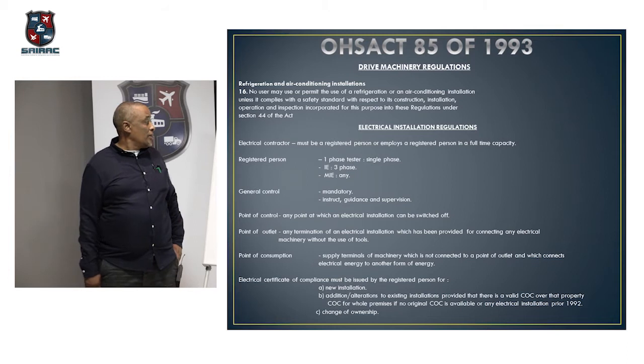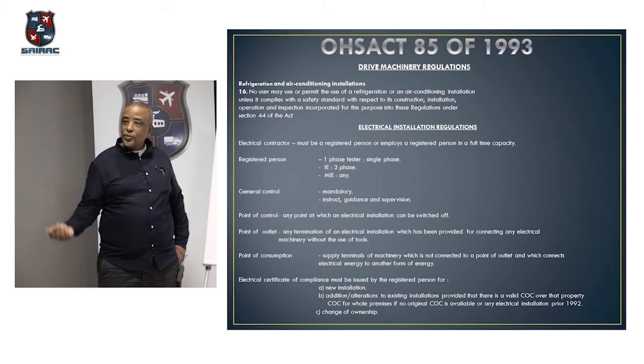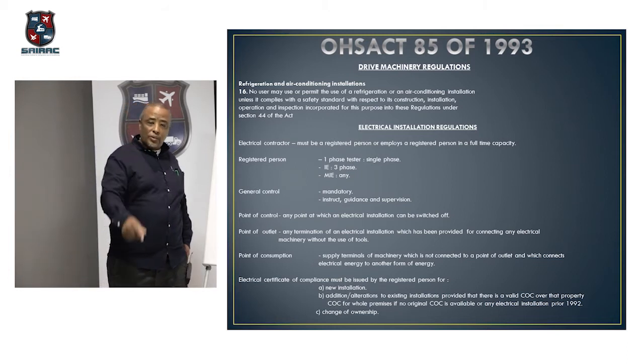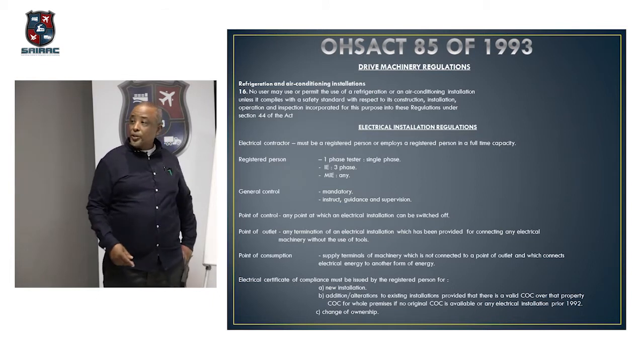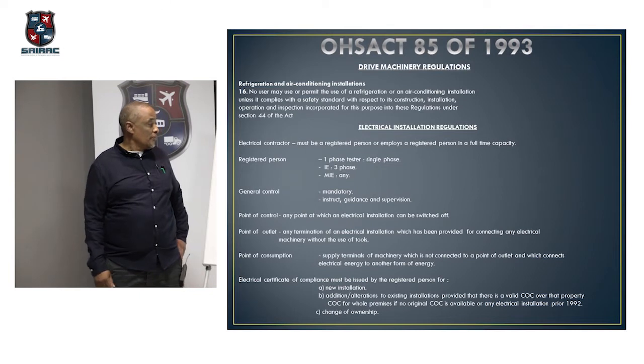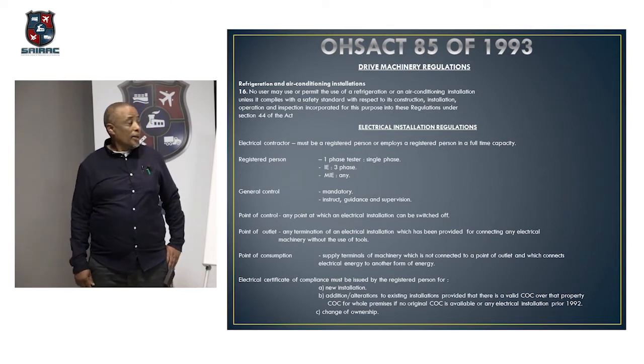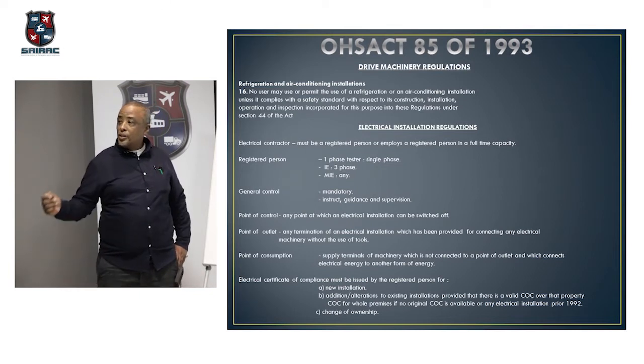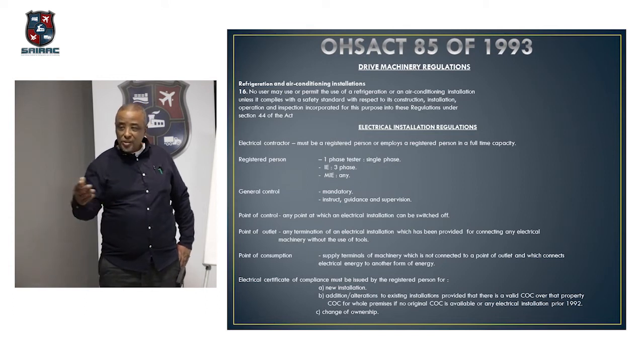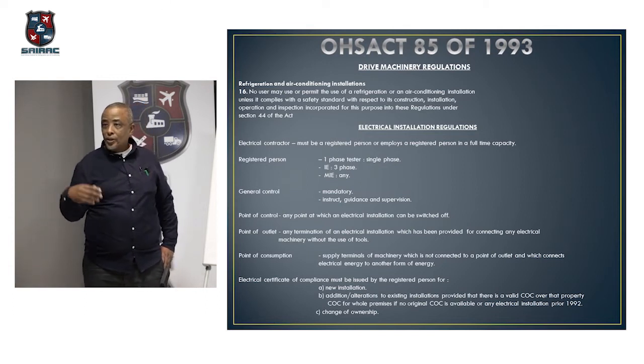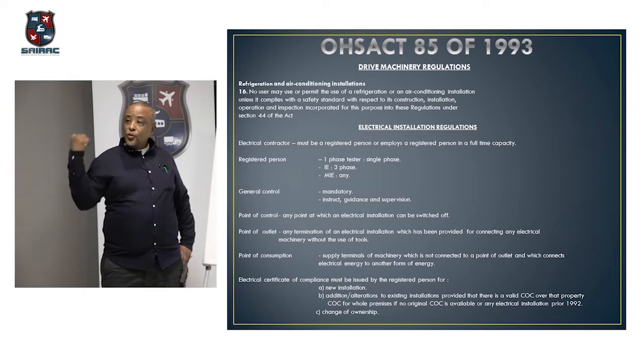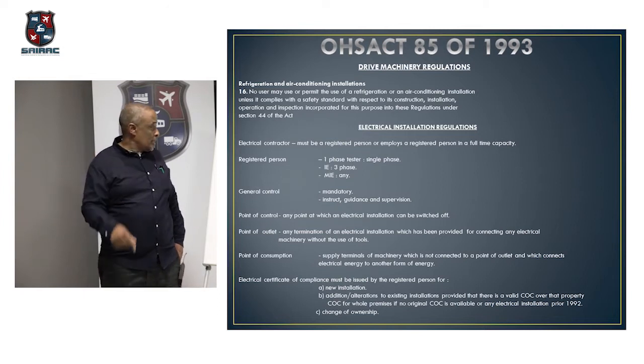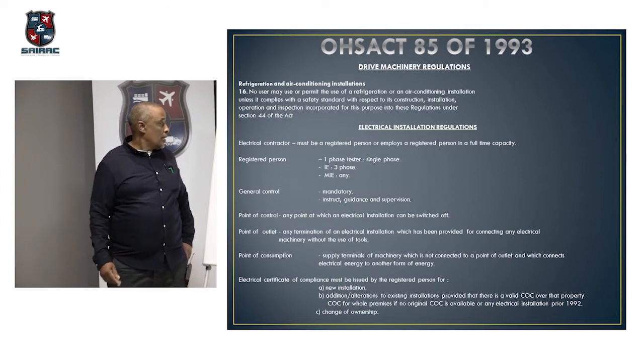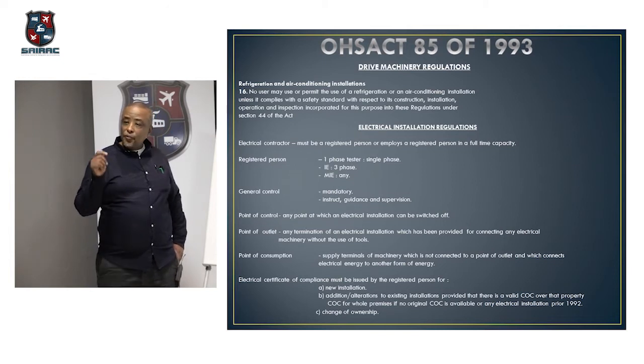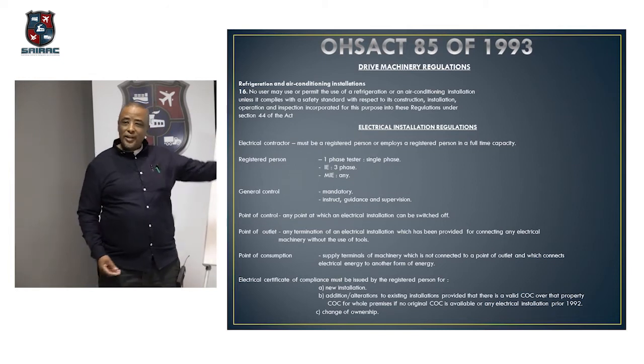It's required for any new installation. When they do an installation, the municipality will switch on for the registered person. He must be on site, must show his card. We'll switch on for him. He tests the installation, and if there are any faults, then he will say, we'll switch off. He's picked up some problems. Okay? The problems could even be on the municipality side, but we'll get back to that part just now.